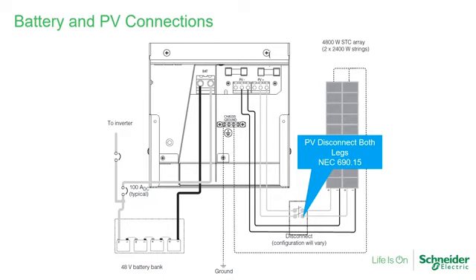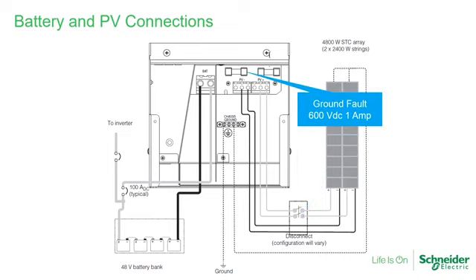Here we have a view of the wiring compartments and what it will look like in the system. The first thing I want to point out is this disconnect, or PV disconnect. To meet NEC 690.15, we must break or open both legs, right? Because this array is going to be 1 or 2 strings max. There are some exceptions in the NEC where, if you meet all of the exceptions, you don't need to have an overcurrent protection device. However, you must have a PV disconnect.